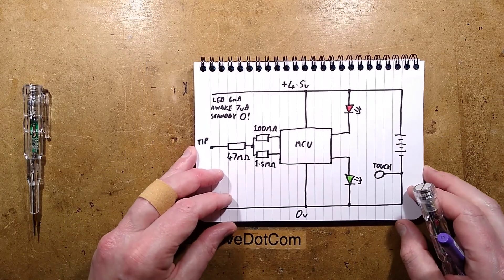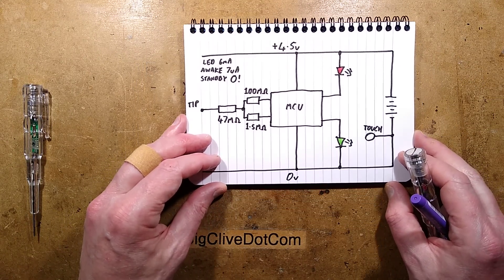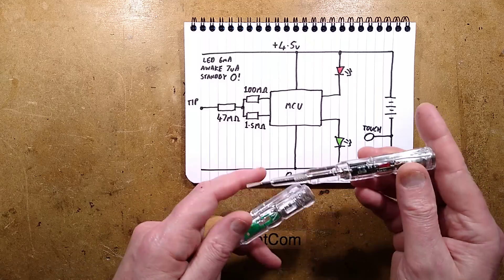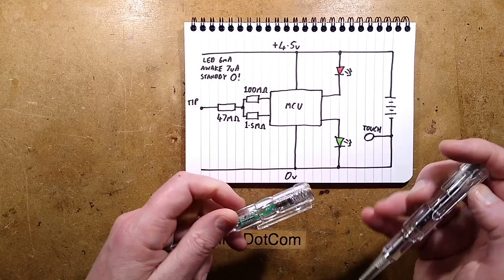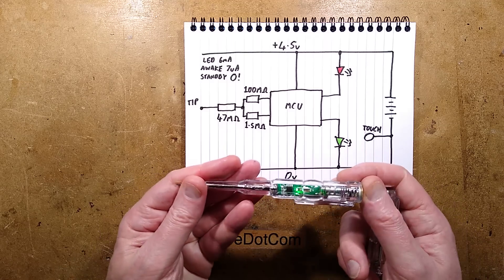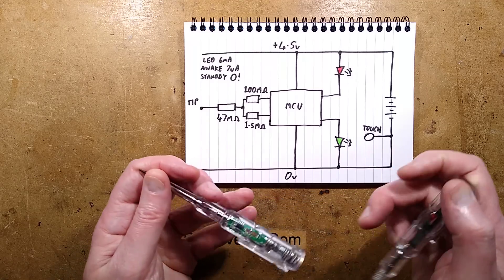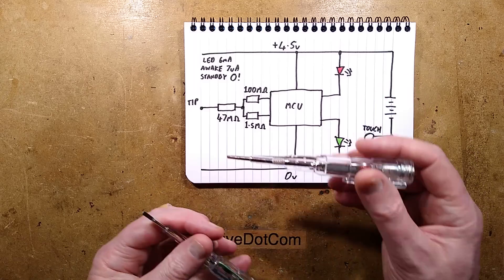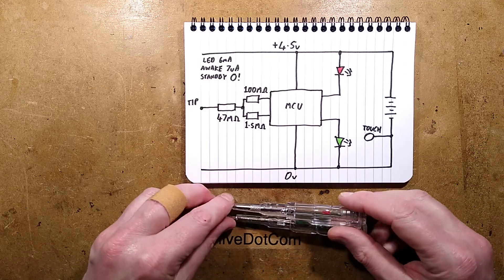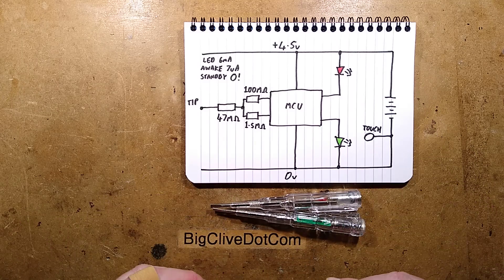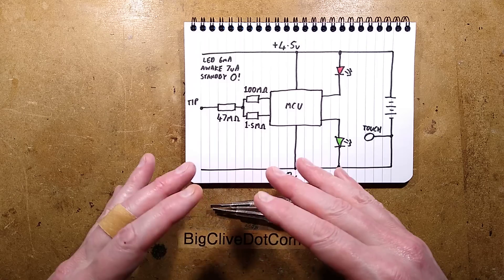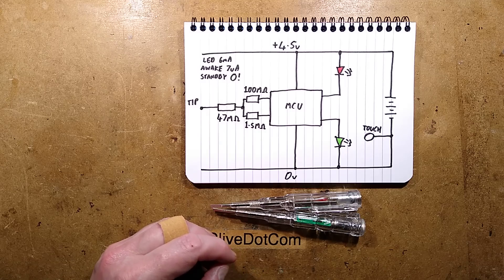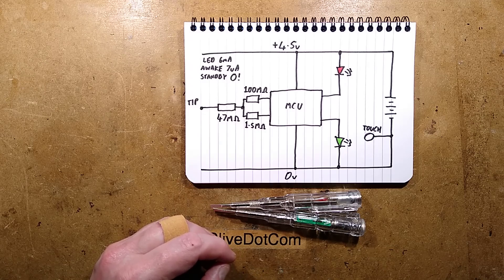I may take a look out for other ones because they seem to be changing the design of these quite a lot. But that's very interesting. They're not that expensive. I don't really rate their electrical separation. But if you ever use one of these, they're good for continuity tests and things like that. But if you ever use one of these, I do recommend not being in a well-grounded environment, not touching grounded metalwork while you're actually using them. I just prefer test lamps and stuff. But these are a good visual check for things like just live wires while you're, just as a double check to make sure you have isolated it. Interesting things. Well worth getting and exploring. Quite unexpected circuitry.